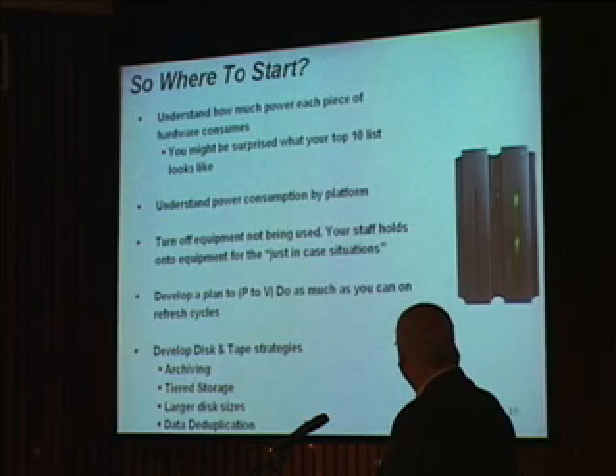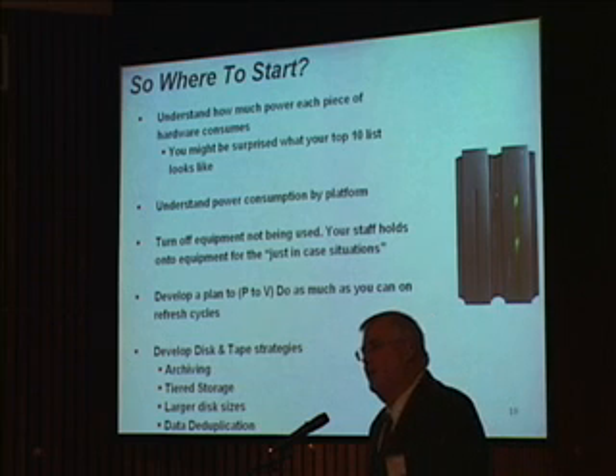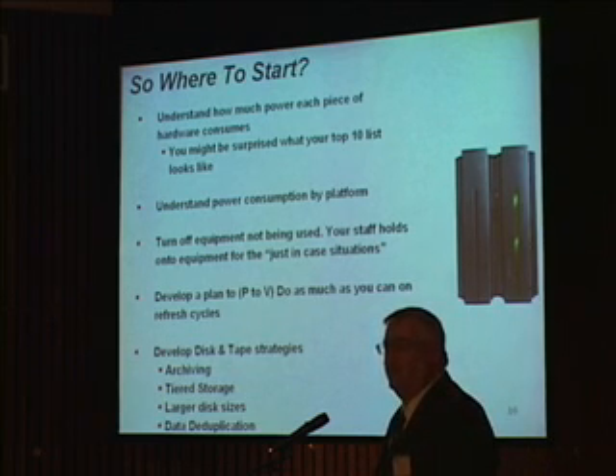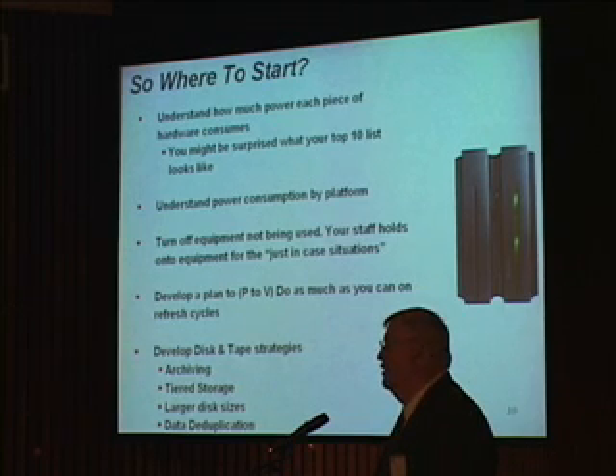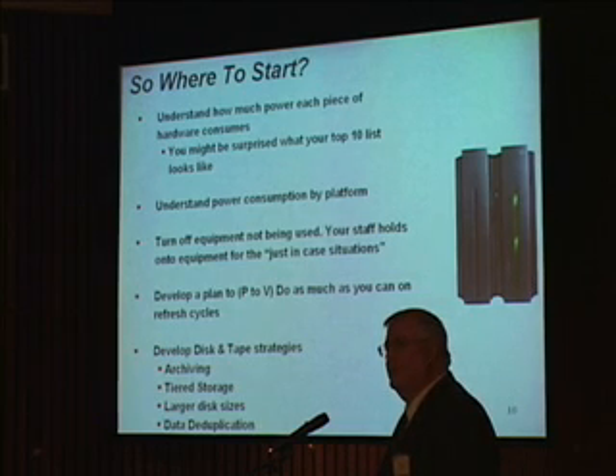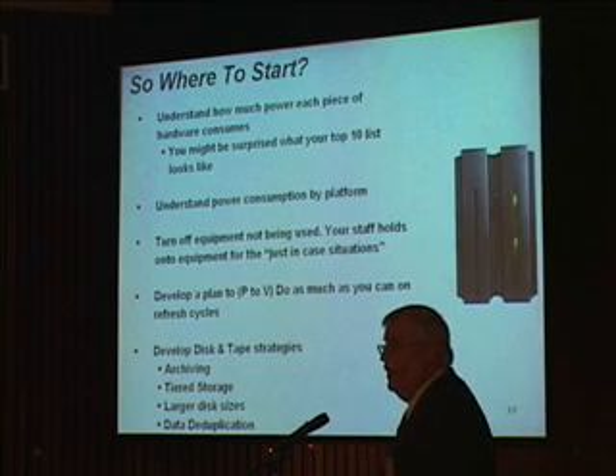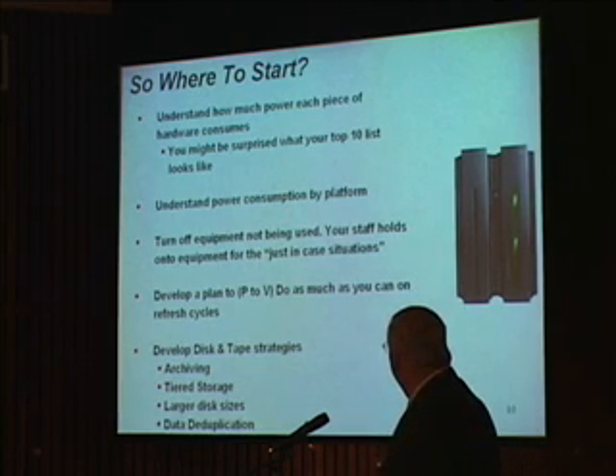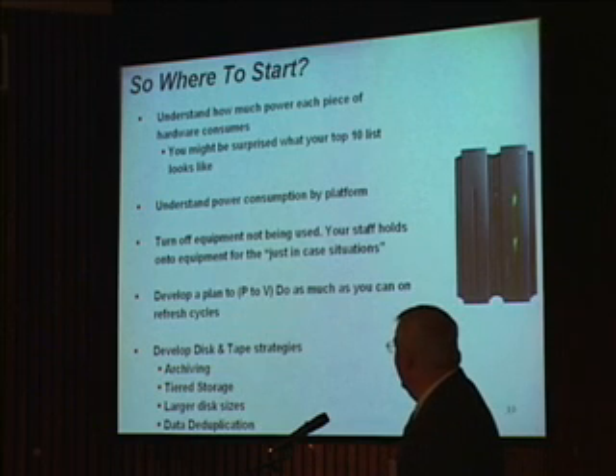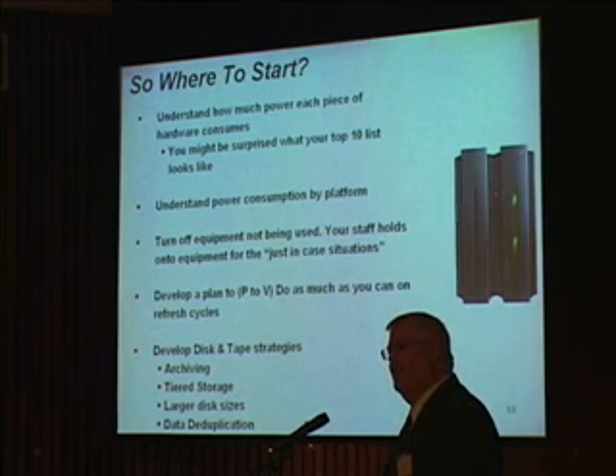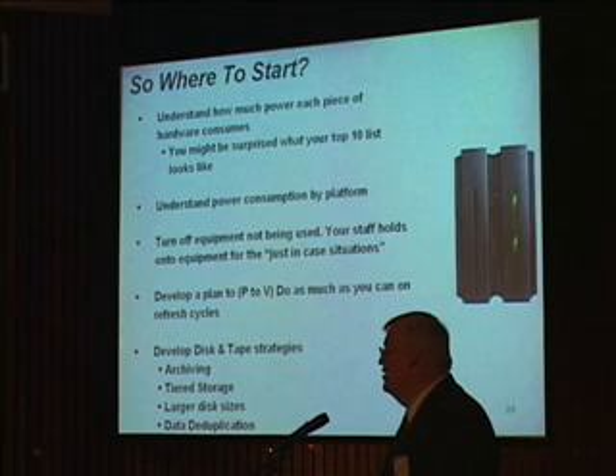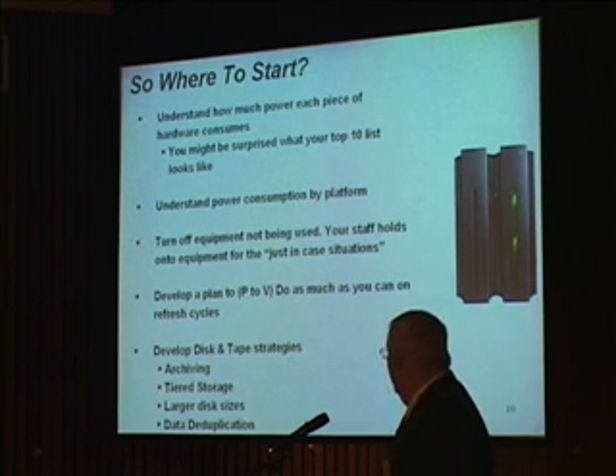So with that, where do we start? We actually went through our data center and measured the power of each piece of equipment. Some things we did actual measurements on, other things we measured plate data. Plate data is not a good measurement, but if you're trying to get a ballpark, you can use it until you get real readings. But having them is important. We tried to understand, out of all these boxes, what platform in your data center is using the most energy. Interesting - we have some slides on that.